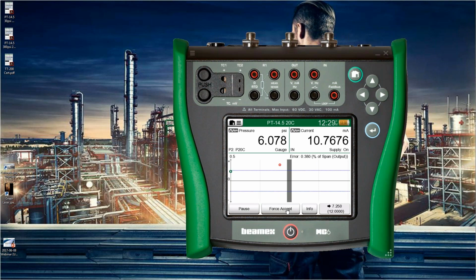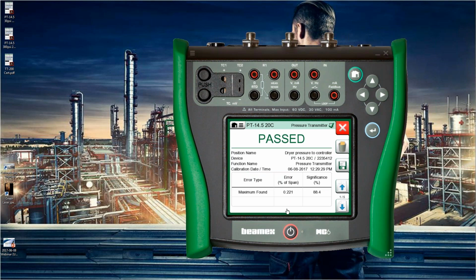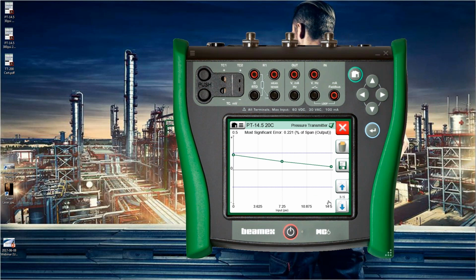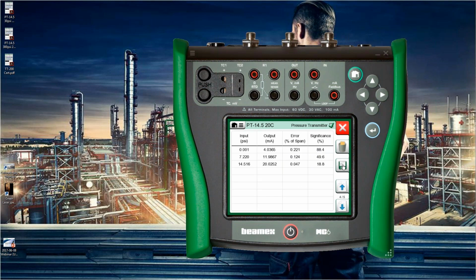And if I were doing this for real, I would actually do an up and down. Pressure tends to have hysteresis more than temperature does. So I would do an up and down test, but for time's sake, we're just going to do a 3-up. And done. All right, so let me set that pressure module down, pressure pump. So we had about the same error, 0.221%. Let me scroll down to look at the graph itself. The graph looks pretty darn similar, and here are the results. Let me save this as well.